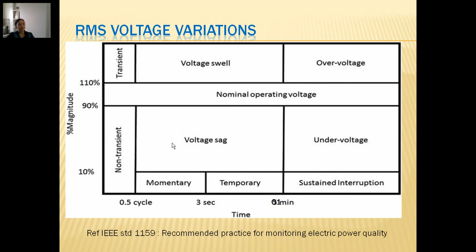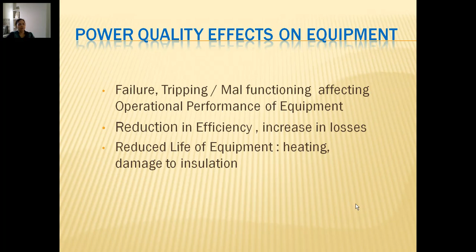The power quality affects equipment, and so failure, tripping or malfunctioning affecting operational performance of equipment is one major concern. Reduction in efficiency and increase in losses is another concern for the equipment, and in short, the life expectancy of the equipment is challenged because of increased heating and damage to the insulation. So equipment is largely affected because of poor power quality.